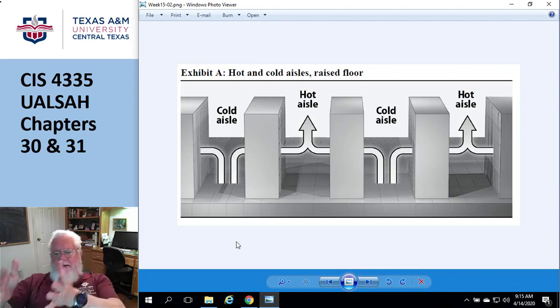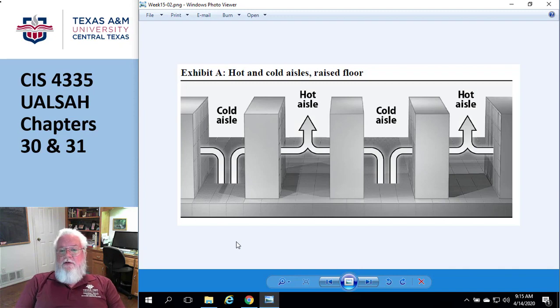So you have a cold aisle and a hot aisle, alternating. This is an interesting way of separating things to maximize cooling, because you never want a rack in the corner getting less cooling than one in the center of the room. That wouldn't work.